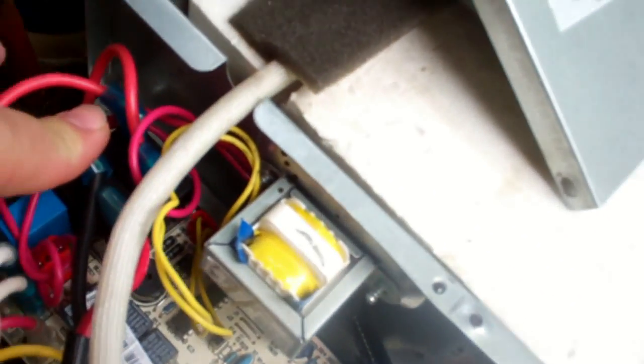There's two here identified as RY6 and RY7. RY6 basically controls the heater, so that's where it's tied in. There's no issue with it. RY7 basically has one wire that goes to P11.